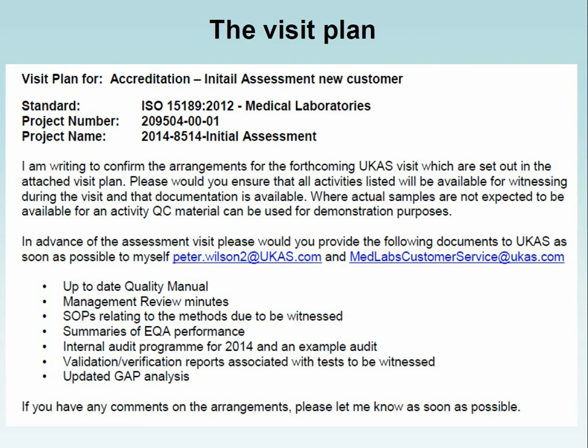So you have to provide them with an up-to-date quality manual, your management review minutes, SOPs relating to methods due to be witnessed, and we'll look at those in a minute. Summaries of your EQA performance, internal audit program for that current year, and an example audit, that's what we had to provide. Validation and verification reports associated with the tests to be witnessed. Updated gap analysis. So they require you to do that gap analysis and document any areas where you believe that you don't meet the criteria. And then, of course, you've had to have satisfied the criteria. So all of those documents go off.